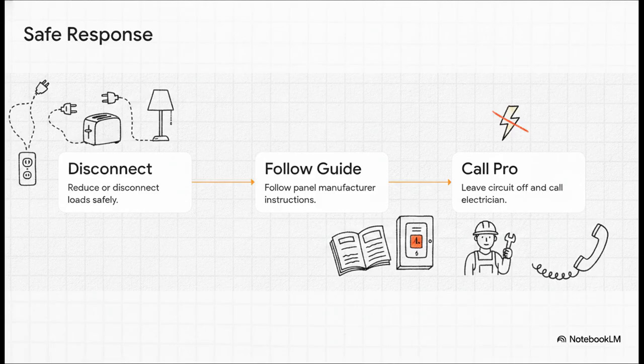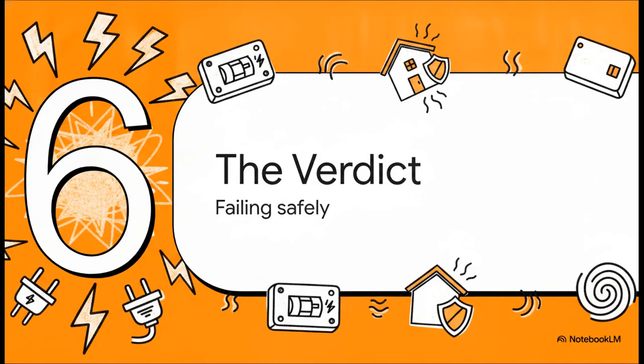Step 1, reduce or disconnect loads safely and only do so without approaching damaged equipment. Step 2, follow your panel manufacturer's specific instructions for resetting. And step 3, if it trips again, or you noticed literally any of those danger signs we just discussed, leave the circuit completely off and call a qualified electrician. Don't mess around with it. And that brings us to the final verdict of our hot summer night mystery.